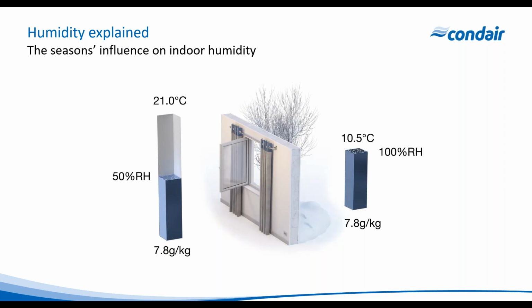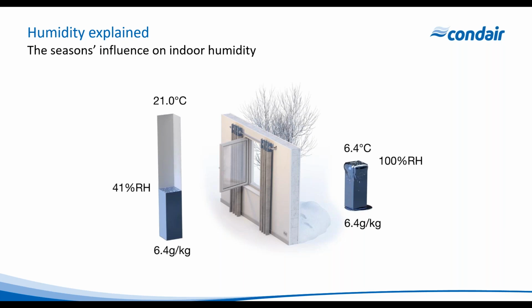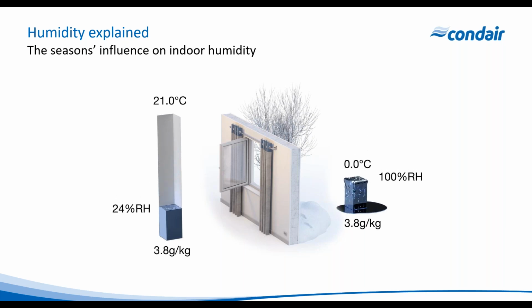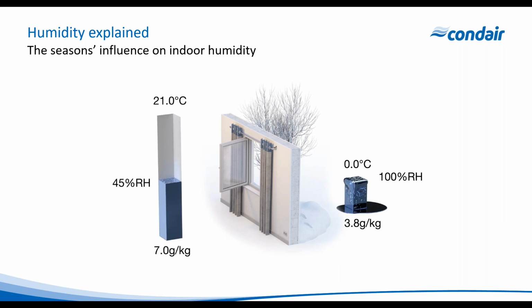However, let's say that now air is going to get even colder as we get into a winter season and the outdoor air condition drops. Here you can see the outdoor air has now contracted and reduced to 0 degrees C. And if we take that air at 0 degrees C, 100% saturated, 3.8 grams, and we put that inside, we're not going to be able to meet the humidity demand in our space. So if we take that 3.8 grams, we're only going to be at 24% RH. So in that case, we have to add moisture to the indoor space to increase the relative humidity up to the desired condition of 50% RH at 21 degrees C and 7.8 grams per kilogram.